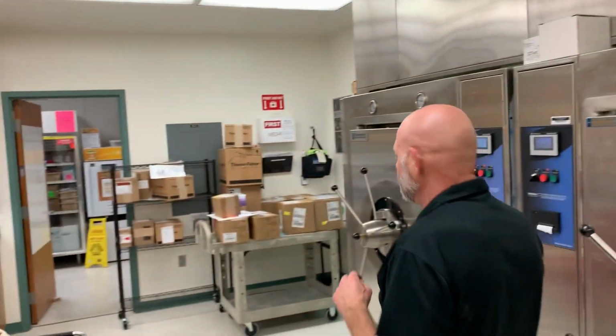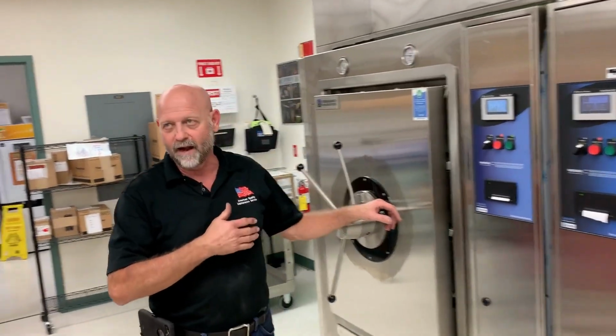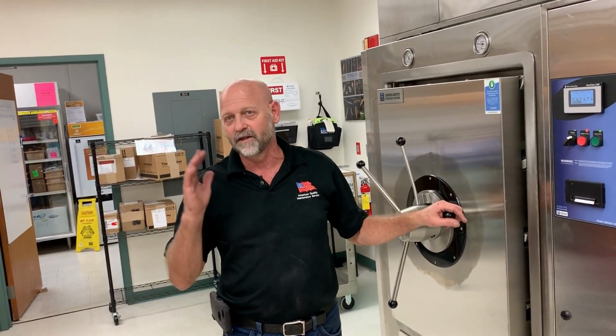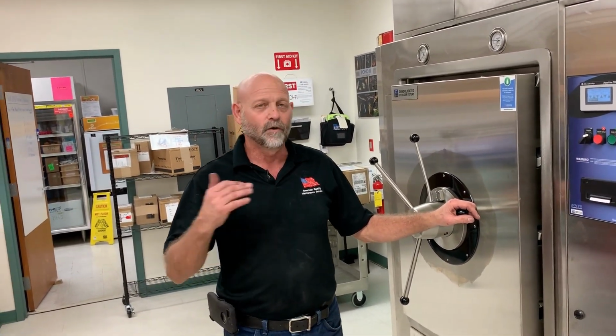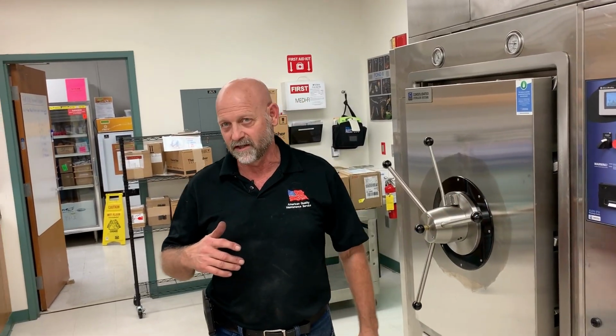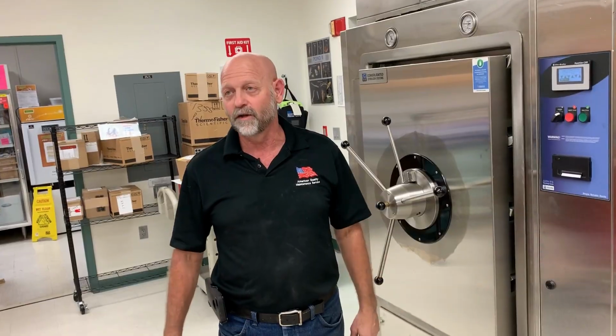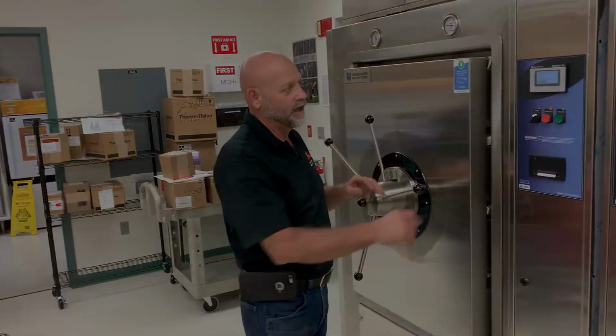Always use a bin with liquids, because liquids can expand and overflow. Also, never do liquids on a gravity cycle, because a gravity cycle is a fast exhaust, where a liquid cycle is a controlled exhaust. If you do a fast exhaust with liquids, more than likely it's going to boil over.